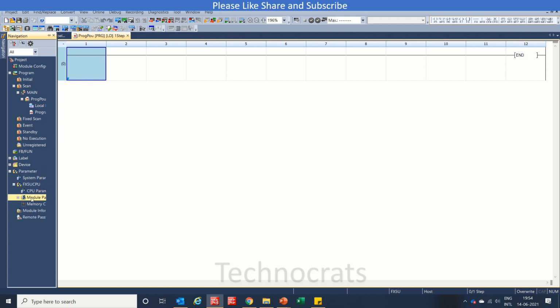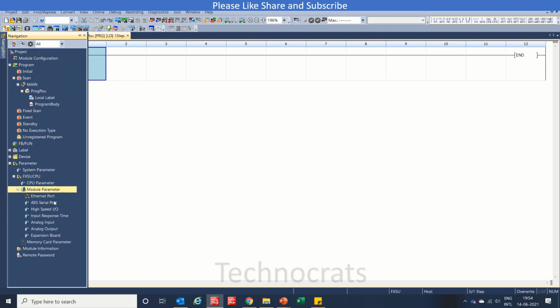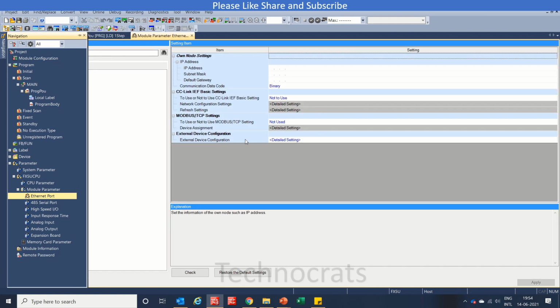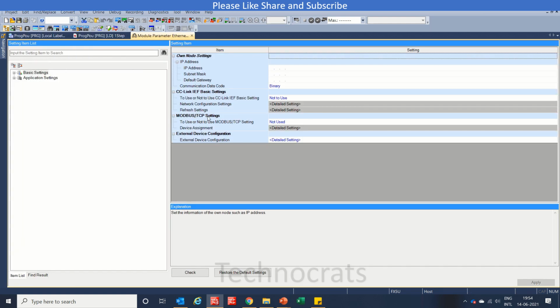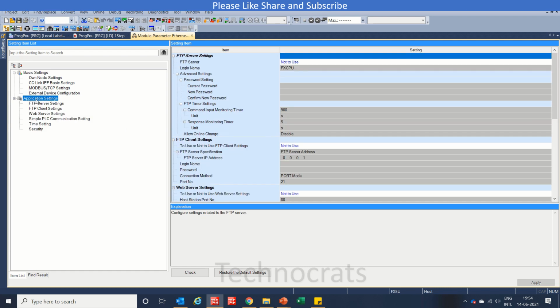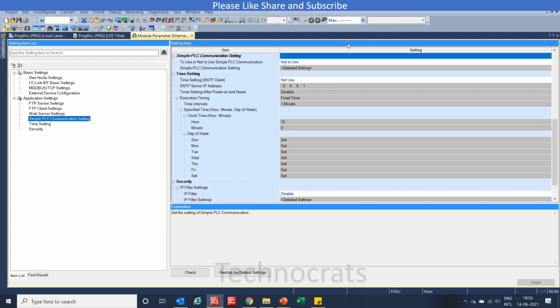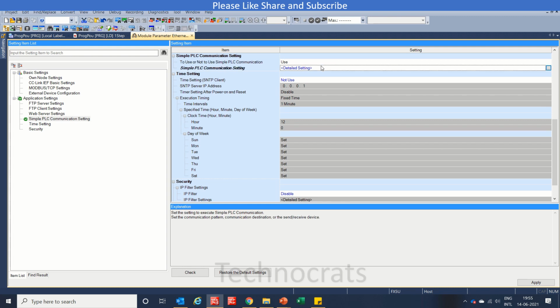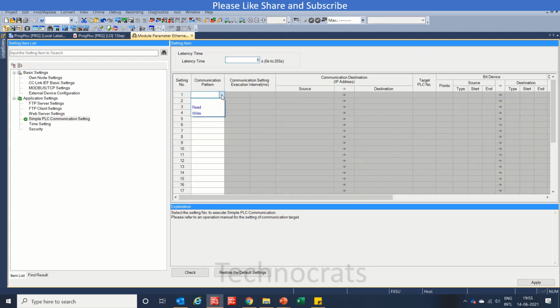So let's see. We'll go to the module parameter, and we have this Ethernet port setting. We'll double click to open. Now as you can see, this is Modbus TCP setting, but this is for your Modbus TCP slave. That means this cannot be set as master. So to set it as a master, you will go to the application part and simple PLC communication. Click here, use detail setting, communication pattern.